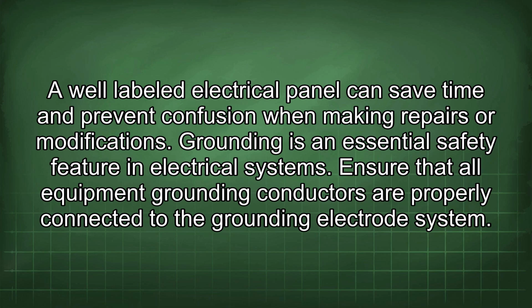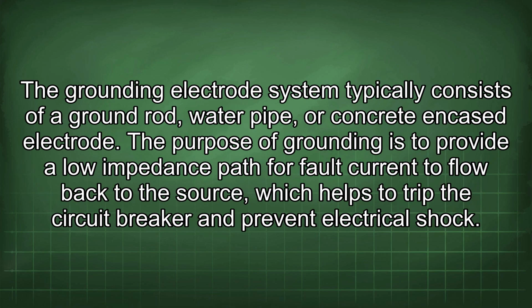Grounding is an essential safety feature in electrical systems. Ensure that all equipment grounding conductors are properly connected to the grounding electrode system. The grounding electrode system typically consists of a ground rod, water pipe, or concrete encased electrode. The purpose of grounding is to provide a low impedance path for fault current to flow back to the source, which helps to trip the circuit breaker and prevent electrical shock.